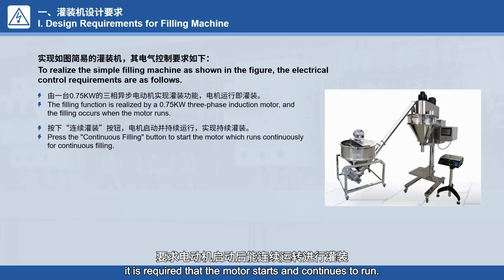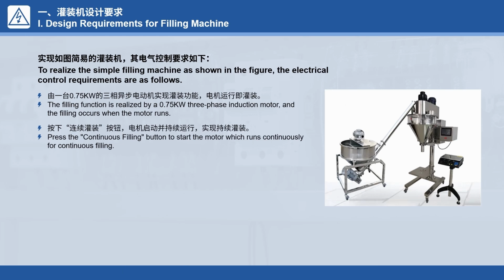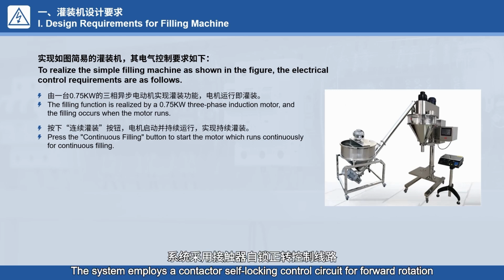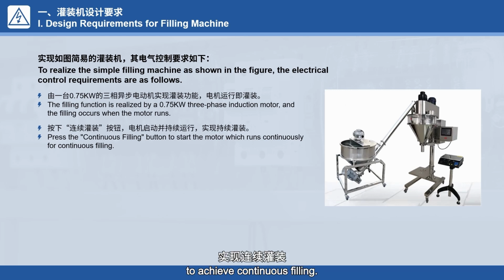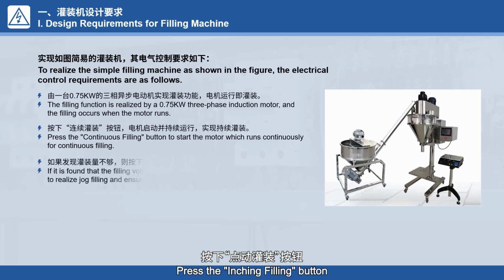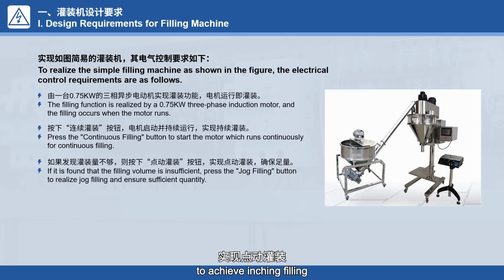During filling, it is required that the motor starts and continues to run. Pressing the continuous filling button starts the motor, which will continue to run. The system employs a contactor self-locking control circuit for forward rotation to achieve continuous filling. Press the inching filling button to achieve inching filling and ensure the correct quantity.